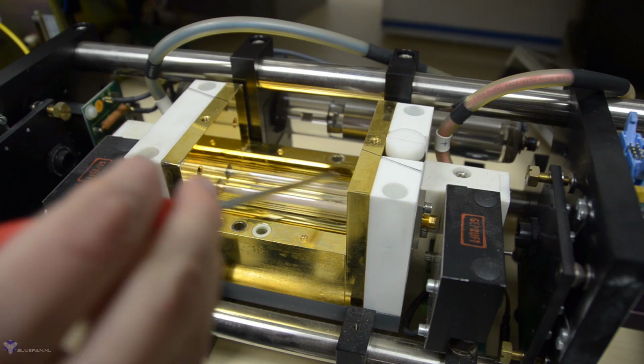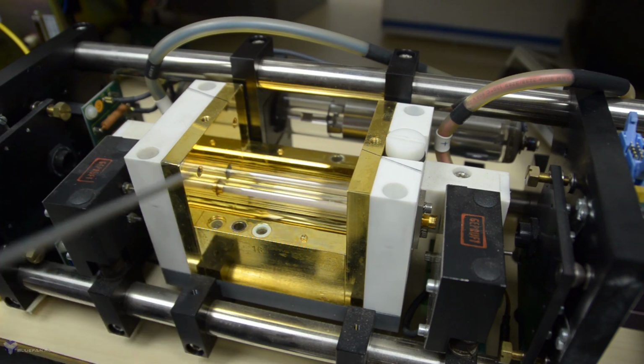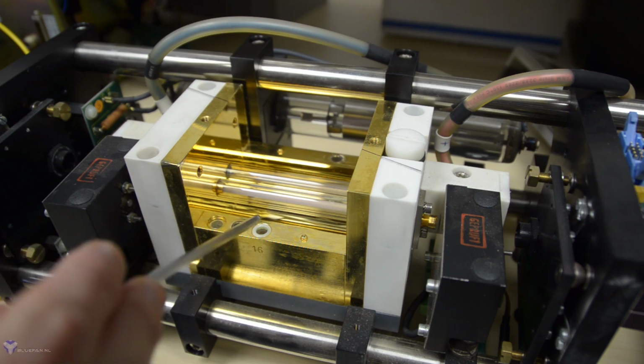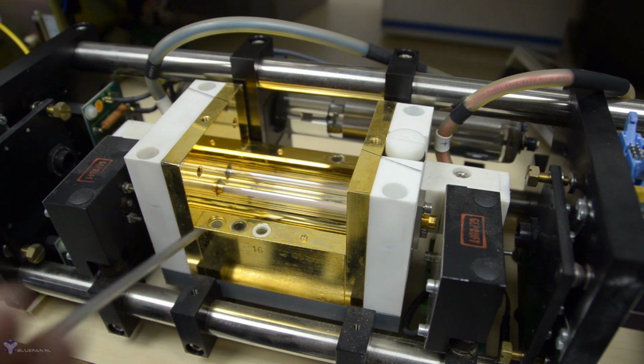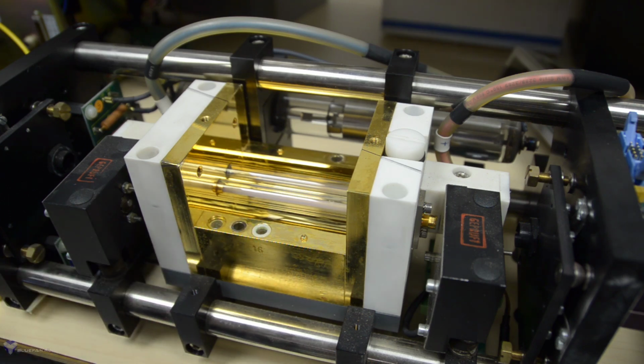Now, at the back you have the arc lamp. It's not a flash lamp pumped laser, it's an arc lamp, it's continuous. And that also is enclosed in a flow tube, because a lot of power is put into that arc lamp and that needs to be cooled away. Now there are two openings here for water cooling, because the reflector cavity itself is also cooled. Now, a lot of power gets dumped into that cavity and it's not 100% reflecting. So some of that power is absorbed and you don't want to have it heat up very strong, so also the cavity itself is water cooled.